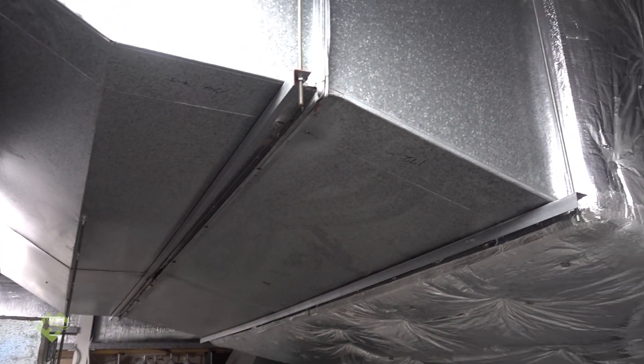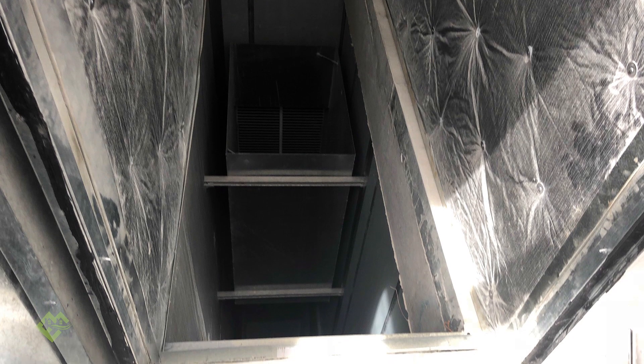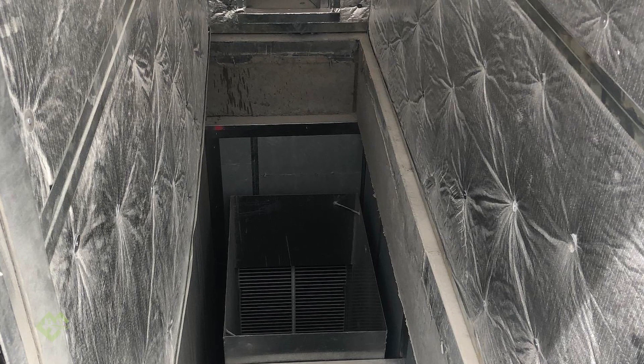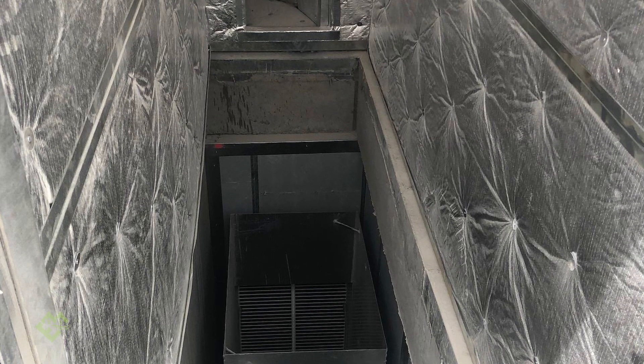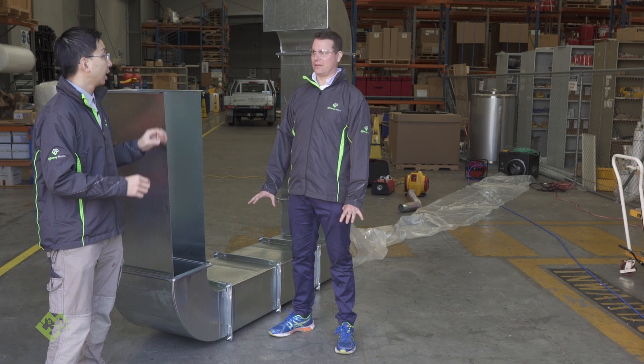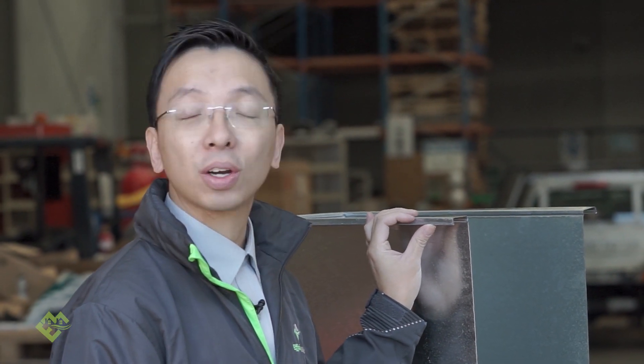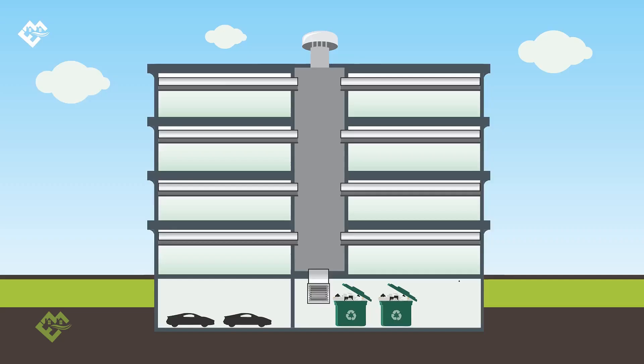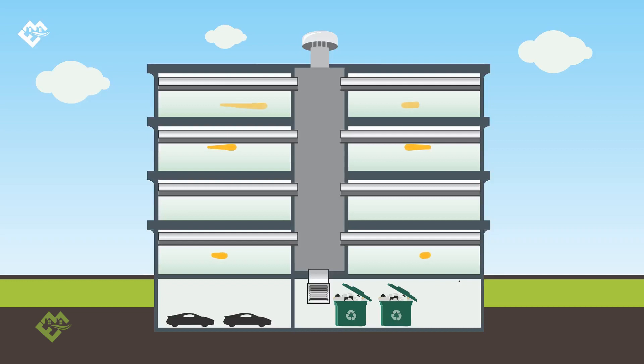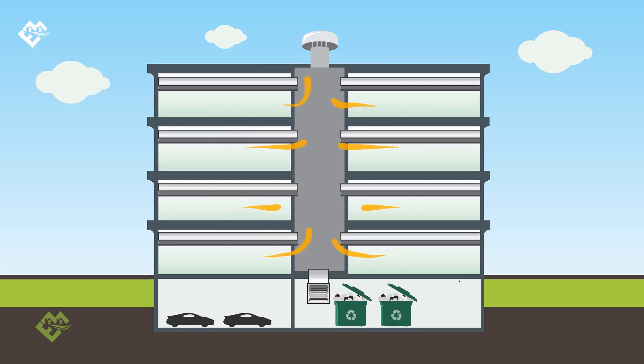For masonry or builder risers — such as speedwall risers — there's no standard dictating what level of leakage is required. However it can cause havoc. In one case we worked on a very simple masonry riser system — a garbage room exhaust in a 25-story building with one inlet and one outlet on the roof — and we got zero pressure down at the garbage room, meaning more than 100 percent leakage.